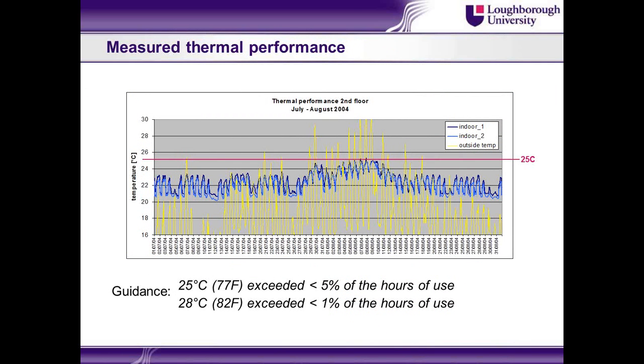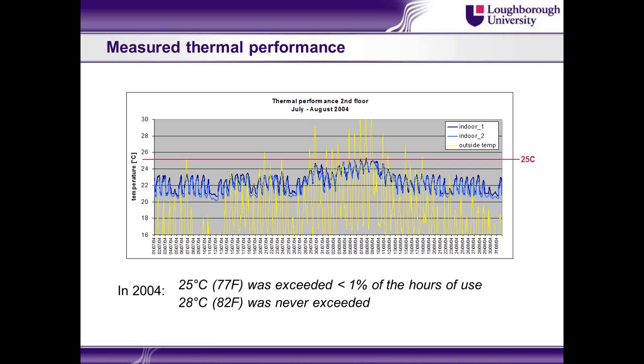Measured performance. Okay, so we had a heat wave in 2004 when the temperature went up to 30 degrees C, it's about 90 degrees F, and that's what I plotted here. So we've got some days in July and August. The yellow is the outside temperature, and the two blue lines are two sensors on the second floor. The guidance we were working to at the time said we shouldn't exceed 77 degrees F for more than 5% of the occupied hours, and we shouldn't exceed 82 degrees F for any more than 1% of the occupied hours. So during this heatwave summer of 2004, 25 degrees C, 77 F was exceeded for less than 1% of the hours, and 82 was never exceeded.